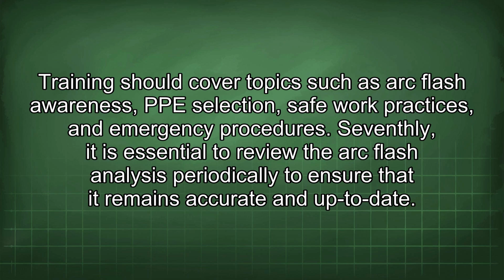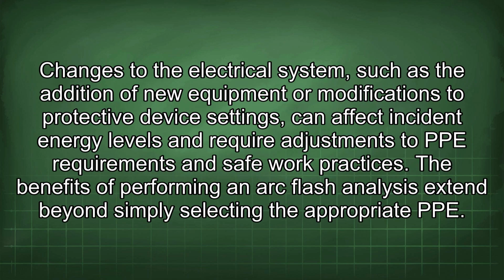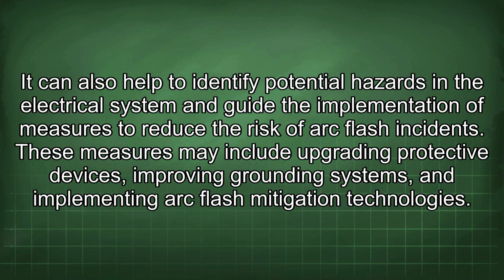Seventhly, it is essential to review the arc flash analysis periodically to ensure that it remains accurate and up to date. Changes to the electrical system, such as the addition of new equipment or modifications to protective device settings, can affect incident energy levels and require adjustments to PPE requirements and safe work practices. The benefits of performing an arc flash analysis extend beyond simply selecting the appropriate PPE. It can also help to identify potential hazards in the electrical system and guide the implementation of measures to reduce the risk of arc flash incidents. These measures may include upgrading protective devices, improving grounding systems, and implementing arc flash mitigation technologies.